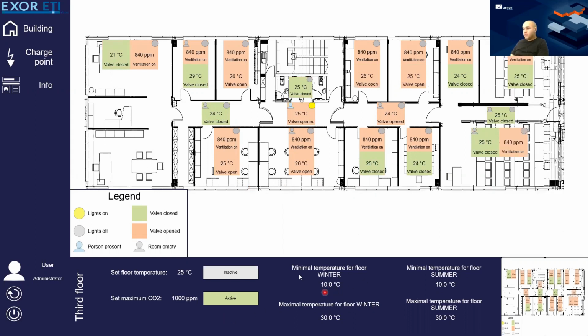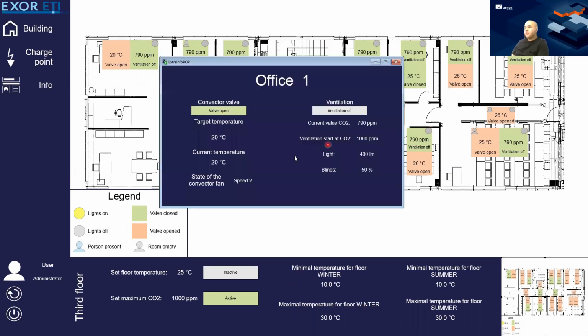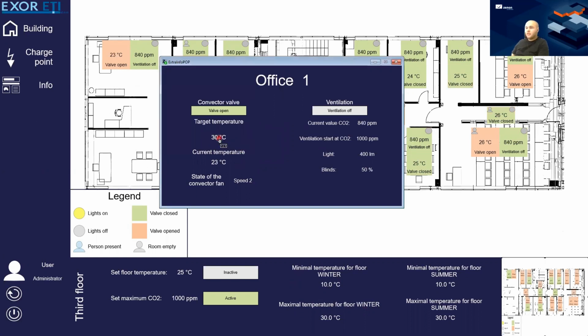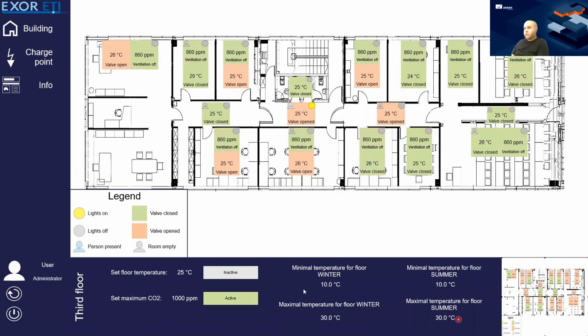Here we have a maximum and minimum temperature setting, in case somebody types in 40 or 50 degrees by accident. The SCADA system prevents unreasonable temperatures from being set. For instance, if we try to set it at 45 and turn it on, it automatically adjusts to 30 and stays there. These limits can also be changed.